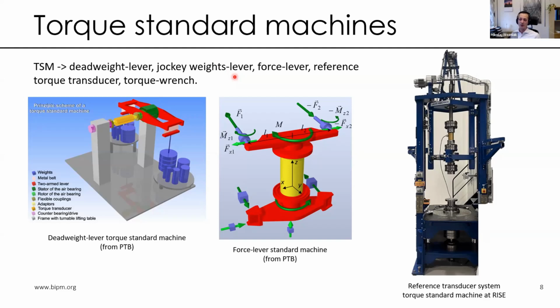We can use semi-primary systems like the force lever system, visible. Its principle is visible here, where you have drives, the cubes here, generating the load, and force is measured. Our forces are being measured by the force transducers, and we can have a lever system with a known length to determine a reference torque. As a secondary system, we can have a reference torque transducer system where a reference torque transducer, as an example, is here, and the object is being mounted below in a specific machine with a stiff frame.